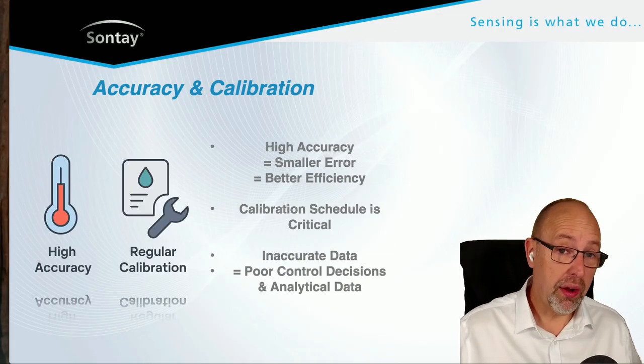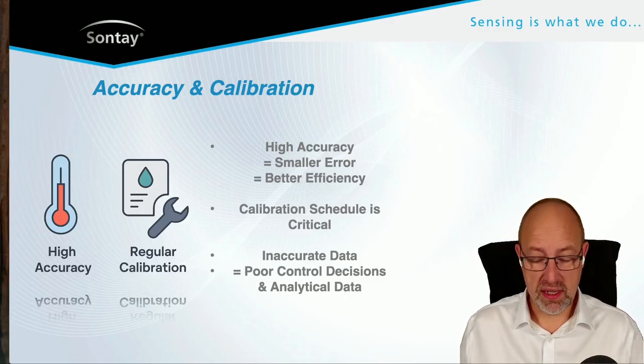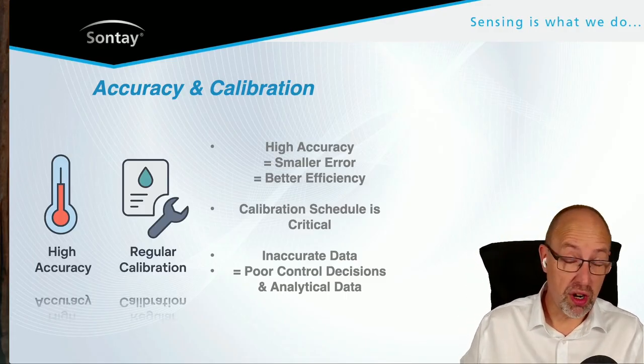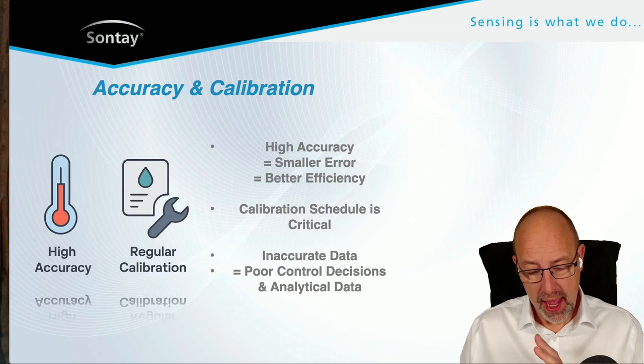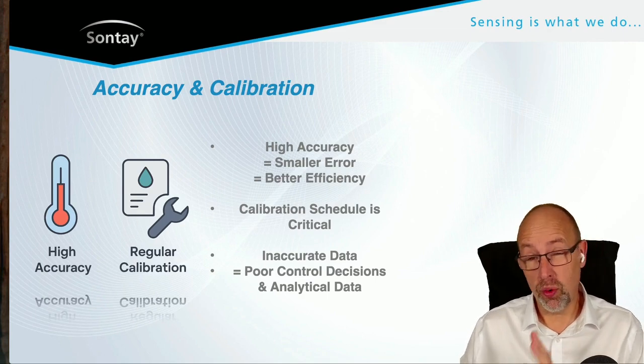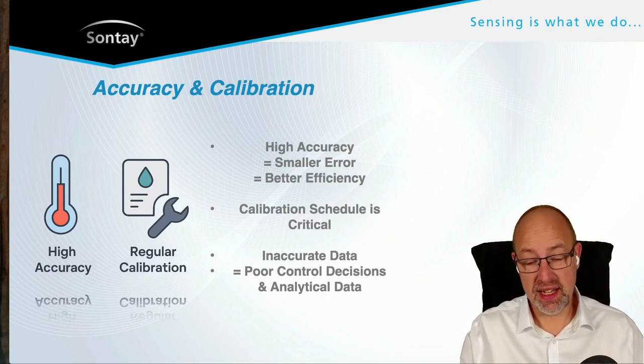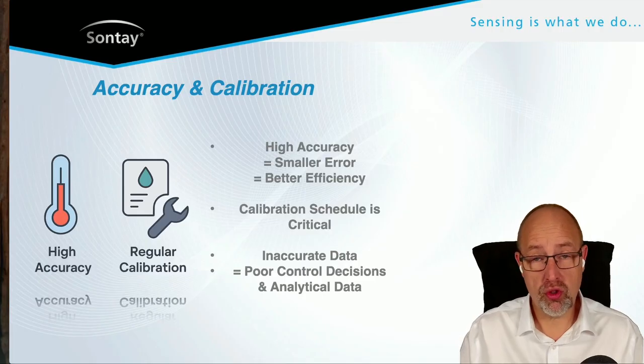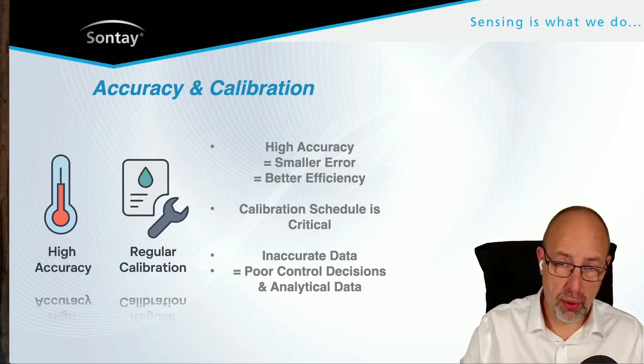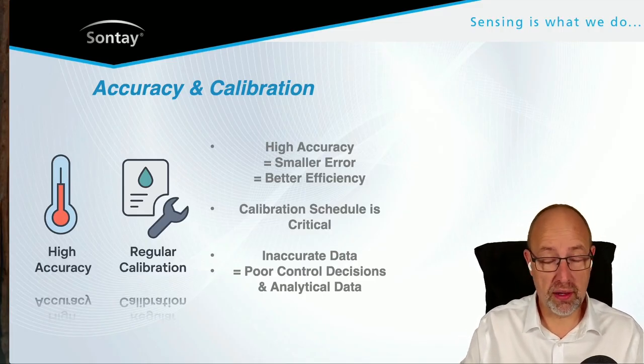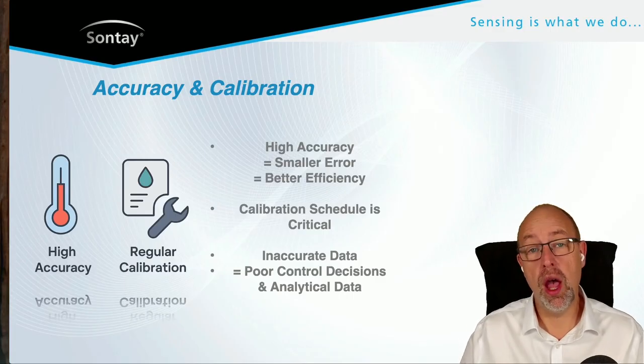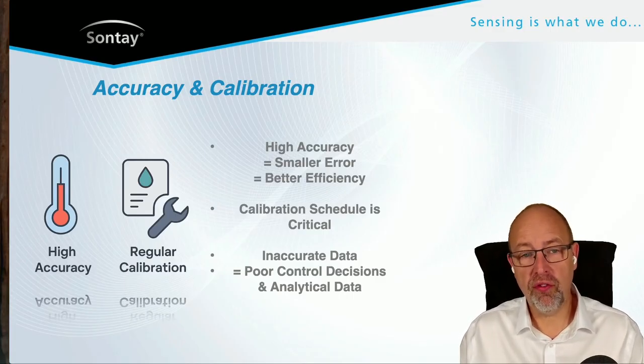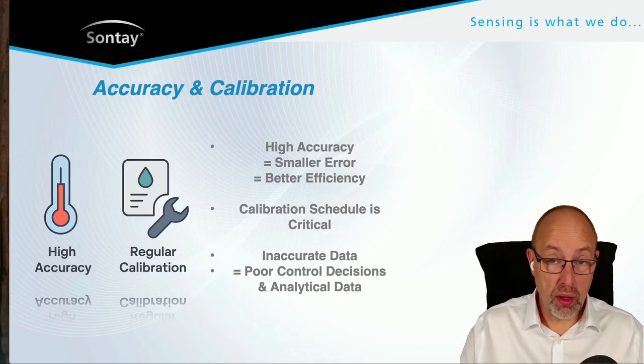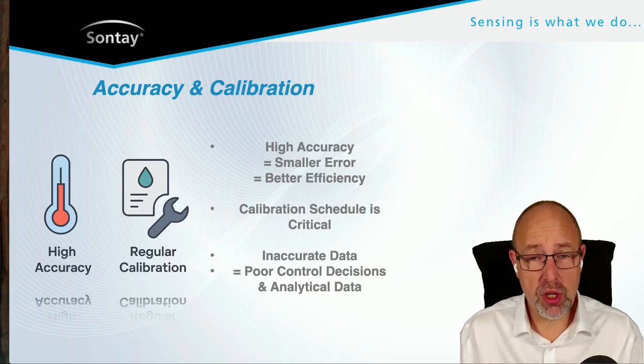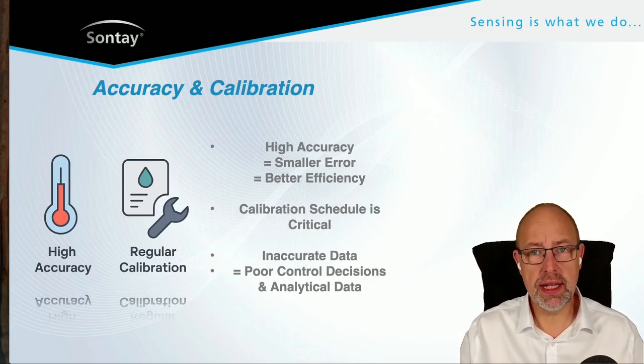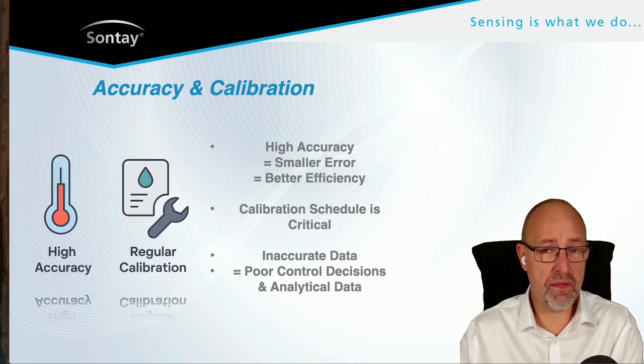This is about the accuracy of sensors and calibration regimes which we should have in place. The reason this is important is that when we're doing very close control - things like pharmaceuticals, laboratories, silicon chip manufacturer or semiconductor manufacturer - we very often are required to have very, very tight tolerances. Everything needs to be, it's often referred to as a validated environment.